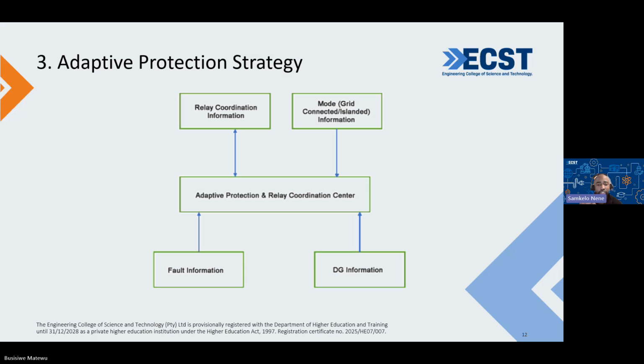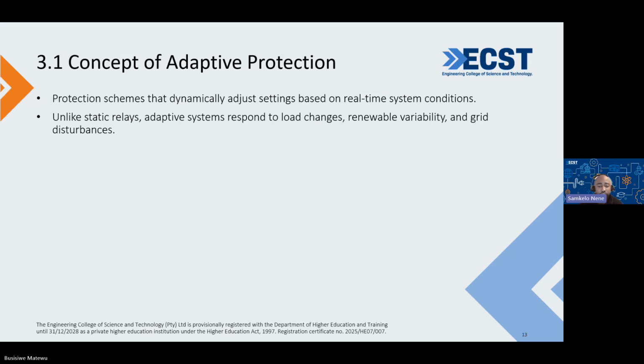With renewables there's more generation, and we'll touch on this when we cover energy storage technologies in the next webinar. Coming back to adaptive protection: these schemes dynamically adjust settings based on real-time system conditions. They use digital relays, which offer programmable logic to facilitate this dynamic adjustment compared to traditional fixed settings. They respond to load changes, renewable variability, and grid disturbances.